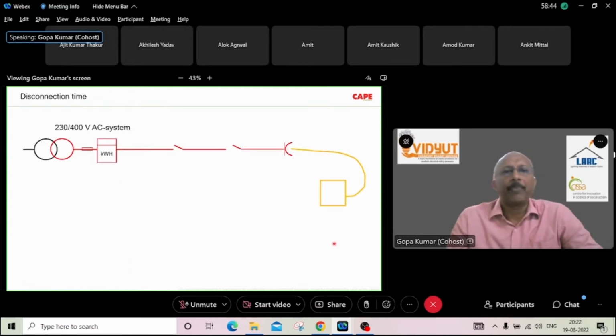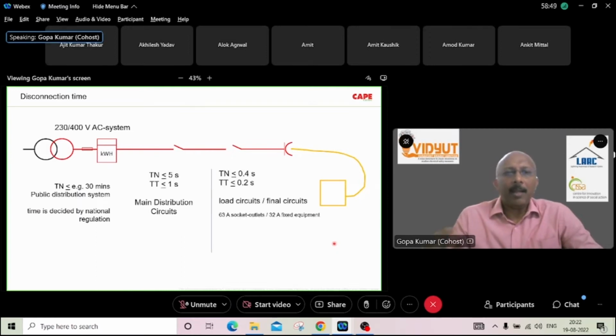Very easy to understand. Now, what is this disconnection time? The electrical system is designed in such a way that from the transformer, here you can see a transformer, you have the meter board, that means after the meter board, you start consuming the electricity. Probably you have a public electricity supply, or you have your own transformer. You have the fixed part of the electrical installation. You have the socket outlet devices and so on. Now, at the final circuits, the maximum allowed disconnection time is 0.4 seconds in case of a TN system and 0.2 seconds in case of a TT system.